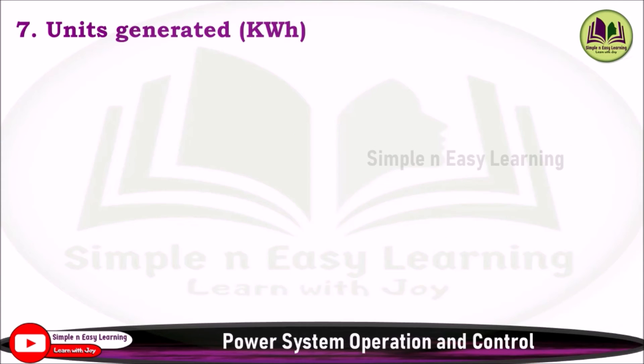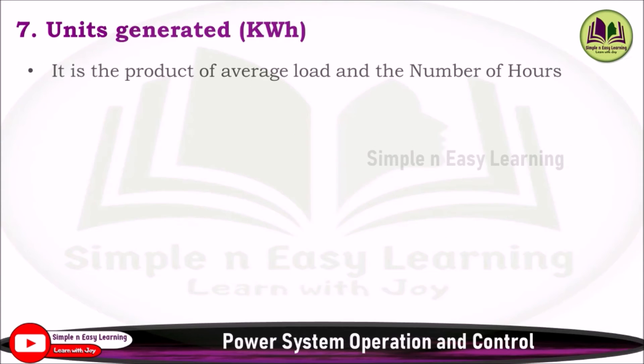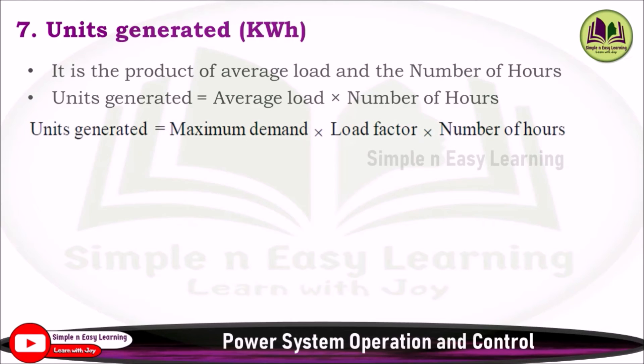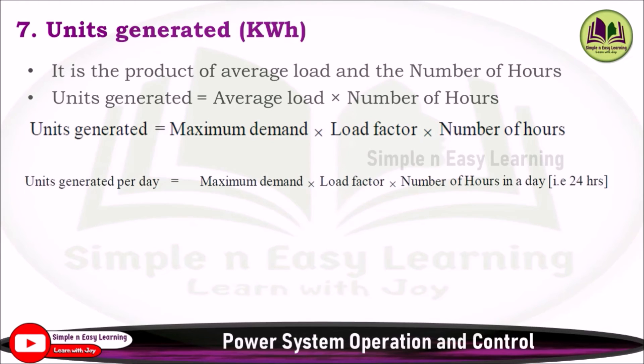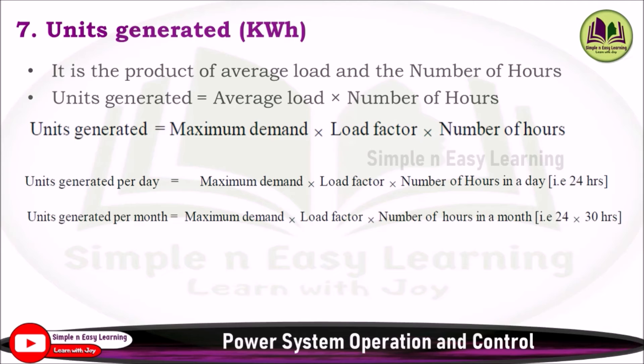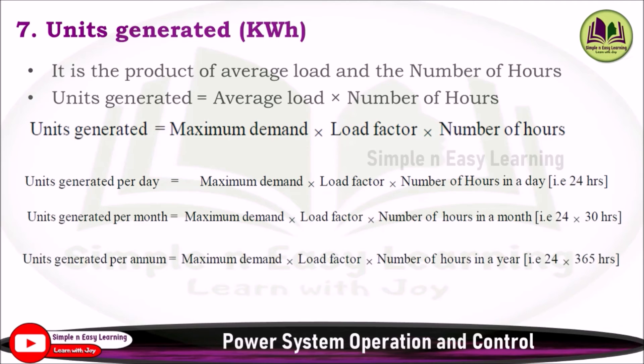Seventh: units generated. It is the product of average load and the number of hours. Since average load = maximum demand × load factor, we get: Units Generated = Maximum Demand × Load Factor × Number of Hours. For daily units, use 24 hours; for monthly, use hours in a month; for yearly, use hours in a year. Use this formula based on the given data.